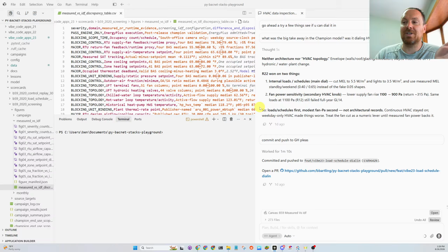And then especially if it's in a place of high demand charges, because in the last write up, the economics were just not there. Because I think the demand charges are just too cheap. And like in the last video I mentioned, I remember hearing people who may work professionally in demand side management full time say that they basically weed out projects. I think for battery systems, if they don't have a $20 per kW charge or something on their utility bills and their rate tariffs, they just know that the ROI won't be there.